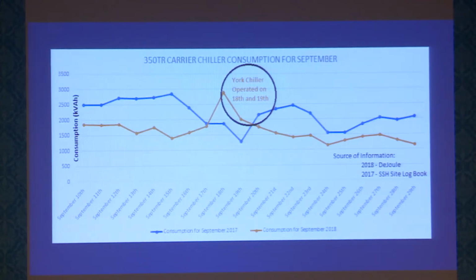The consumption there is 2,500. In 2018, we put our BMS in the facility and started monitoring and controlling the chiller. As a result, 700 units were saved on a particular day. 700 units into 10 rupees is 7,000 rupees per day, into 30 days is 2,10,000 rupees per month - just by changing the set point of the chiller.